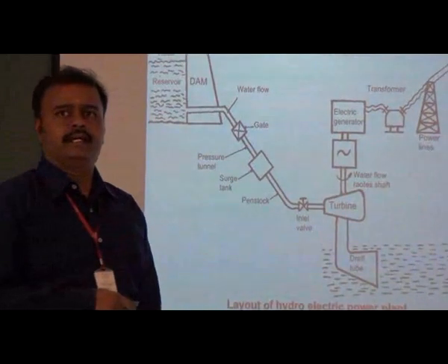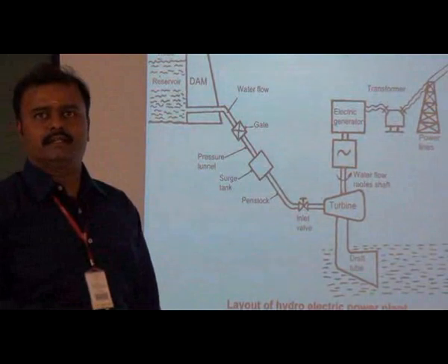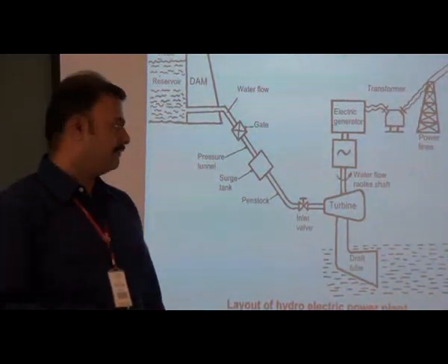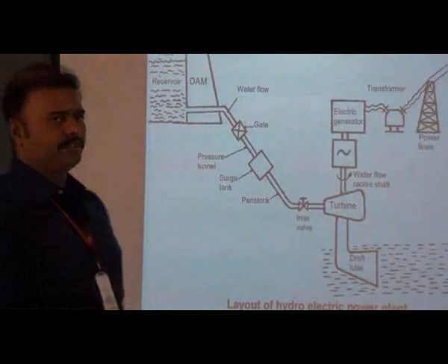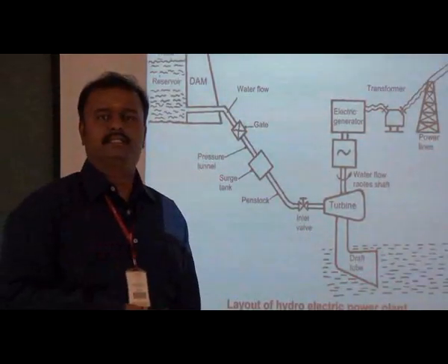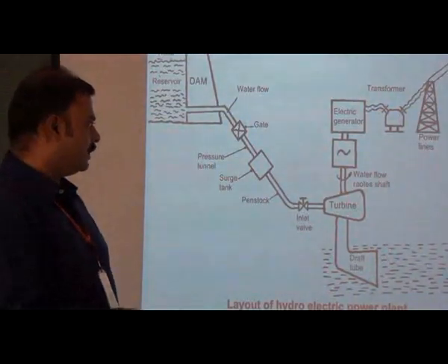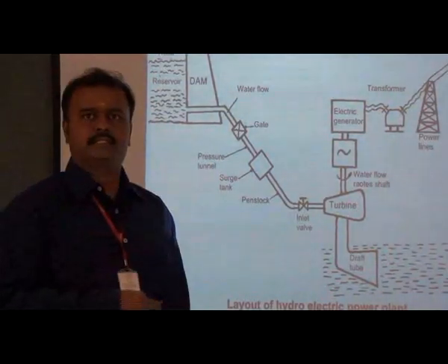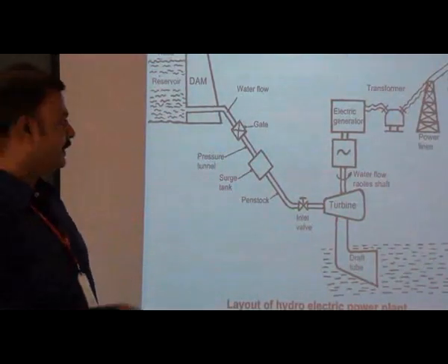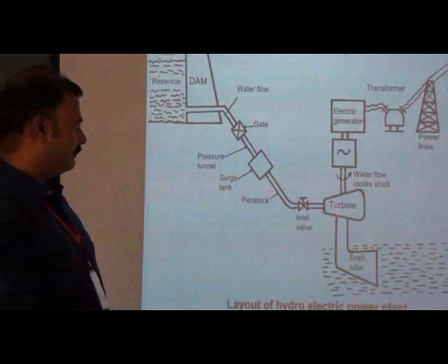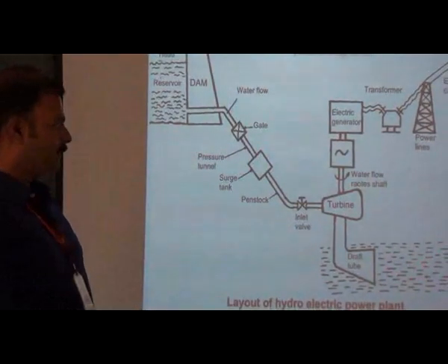The exhaust water coming from the turbine also has a huge amount of velocity. So we cannot directly allow that water into the river, because the living things in the river would be affected. To avoid that, we use something called a draft tube. The draft tube is a diverging section. Here the velocity of the water coming from the turbine is reduced and converted into increased pressure. So all the water coming from the turbine is mixed with the river and goes directly into the river.